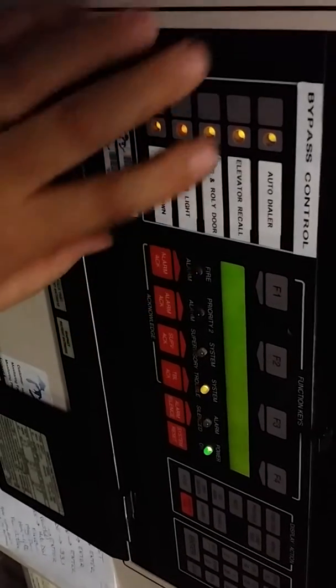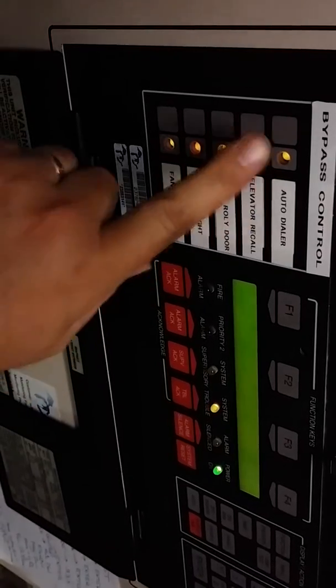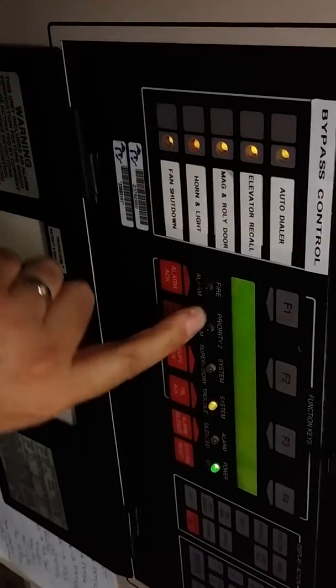Now, if this is an alarm, you do not take the auto dialer off at all. Because if this is an alarm, as soon as you undo these, you'll hear everything go off in the building, and the fire department will be coming. So even if you were running through a test, say we took it offline because we knew that we might set off a smoke detector, you have to make sure that you do a system reset before this. You have to make sure no red lights.